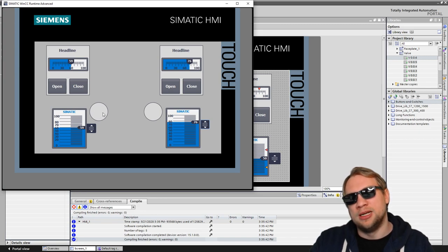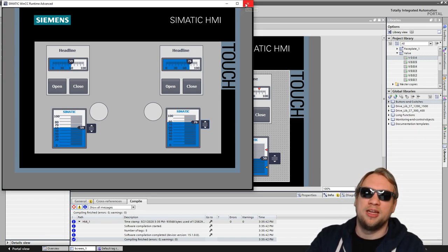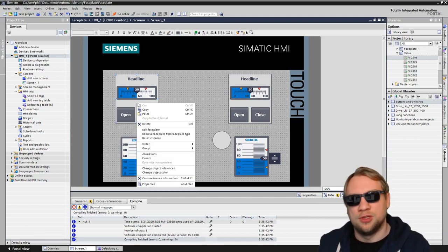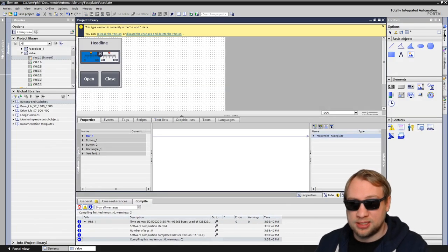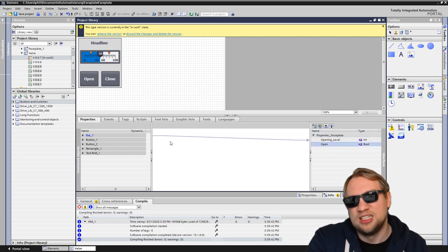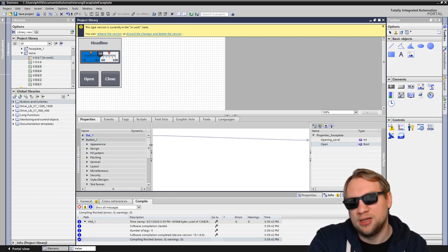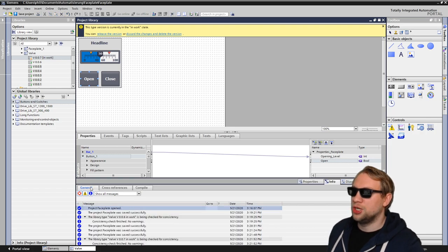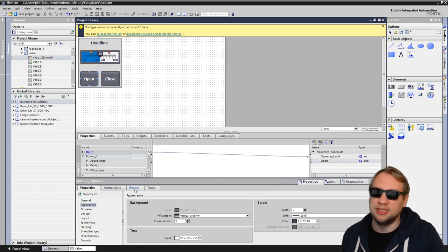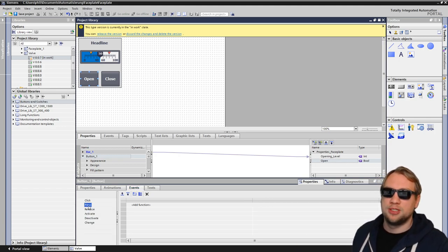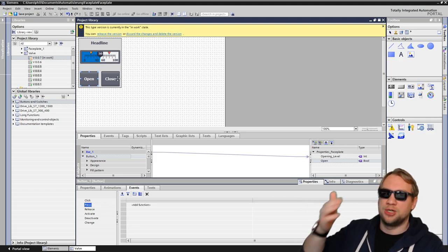The second one is this little LED. Let's call this an LED - it should indicate if the valve is open or closed. The variables are already linked. What we need to do is go into the faceplate, edit the faceplate, and make that change. We have this open variable on the right side - that is connected to everything. What we still need is to connect both buttons to it. Here on the left side I have the button and there are many things I can do with it. Down here in our inspector window, if you click on the button you will see under general no properties, and there you have events. That's the same as always. So I go to events and there I have my press event - if this button is pressed, the valve should open; if this button is pressed, the valve should close. Let's just do that.